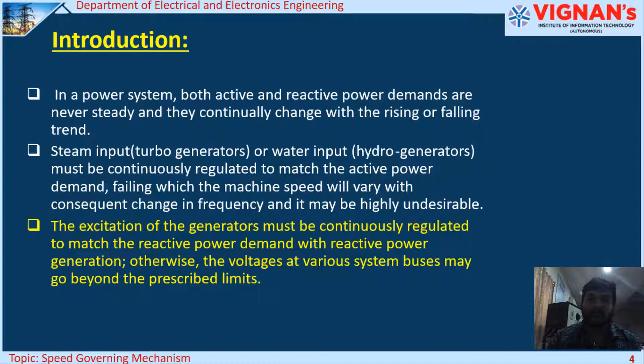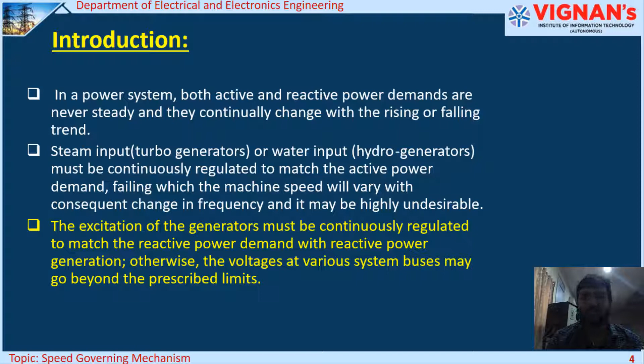However, the excitation control can be used to improve the voltage at a particular bus or reduce the voltage at a particular bus by compensating for the reactive power that is available at the load. And you have to maintain all these constraints. So all the maximum and minimum limits for the real and reactive power and the voltage limits must all be maintained in a constrained environment.